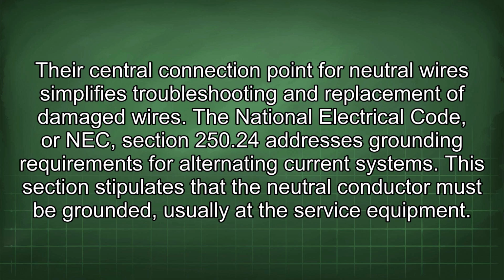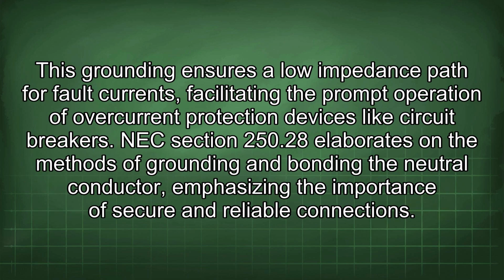The National Electrical Code, or NEC, Section 250.24 addresses grounding requirements for alternating current systems. This section stipulates that the neutral conductor must be grounded, usually at the service equipment. This grounding ensures a low impedance path for fault currents, facilitating the prompt operation of overcurrent protection devices like circuit breakers.